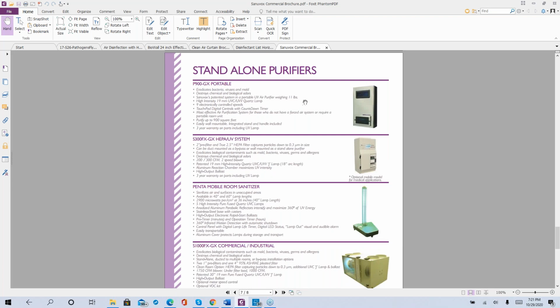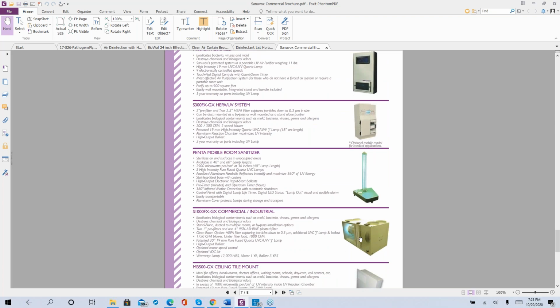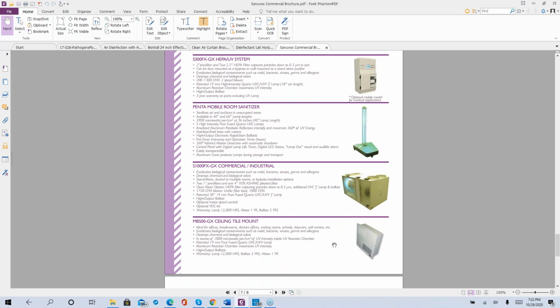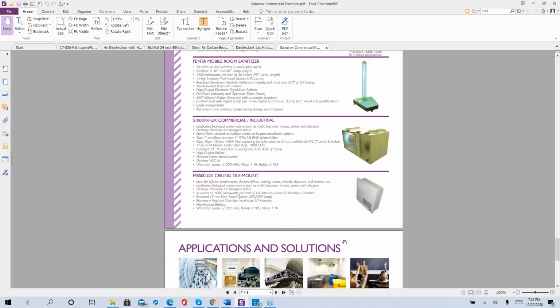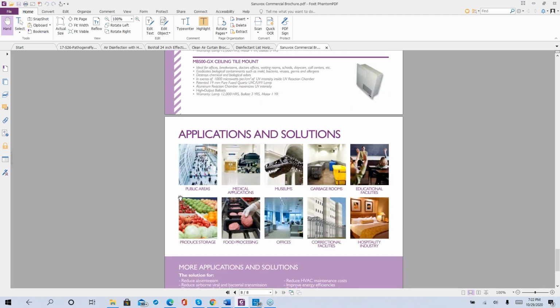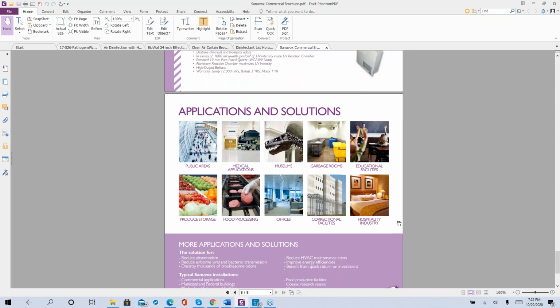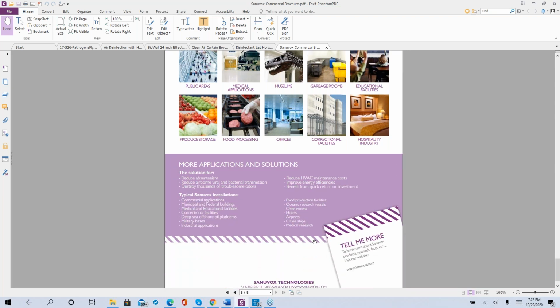Here's some of the other things that they do for the standalone purifiers. The portable can be like a side stream filter. You can mount it on the return air. They have this mobile room sanitizer, and then they've got this behemoth that you could put in a room if you wanted to and get up to 1,000 CFMs. This is no longer the ceiling tile mount. That's no longer manufactured. That would have been a great thing. So these are some of the things that they believe they can help you with. And like I say, go to Sanuvox.